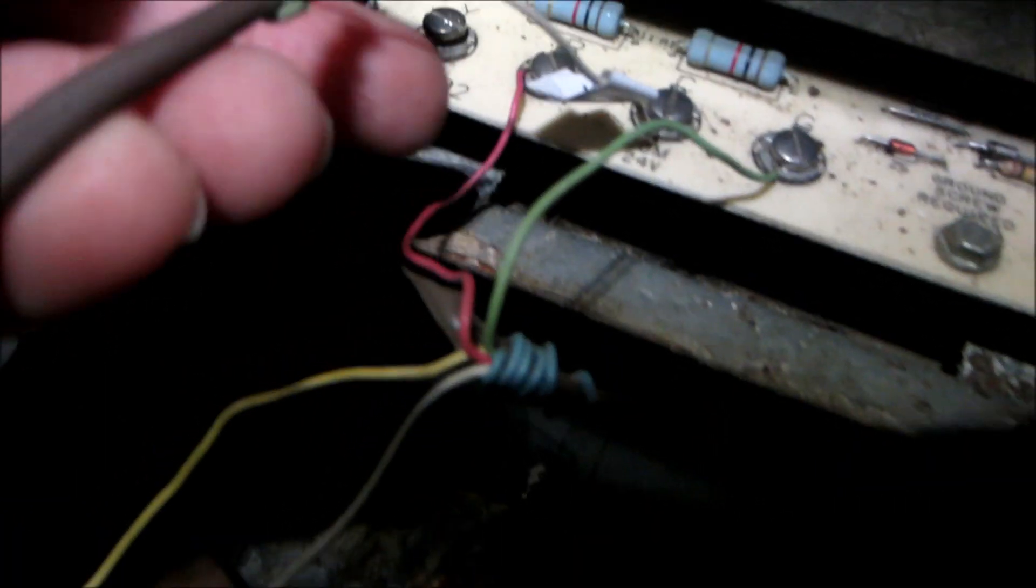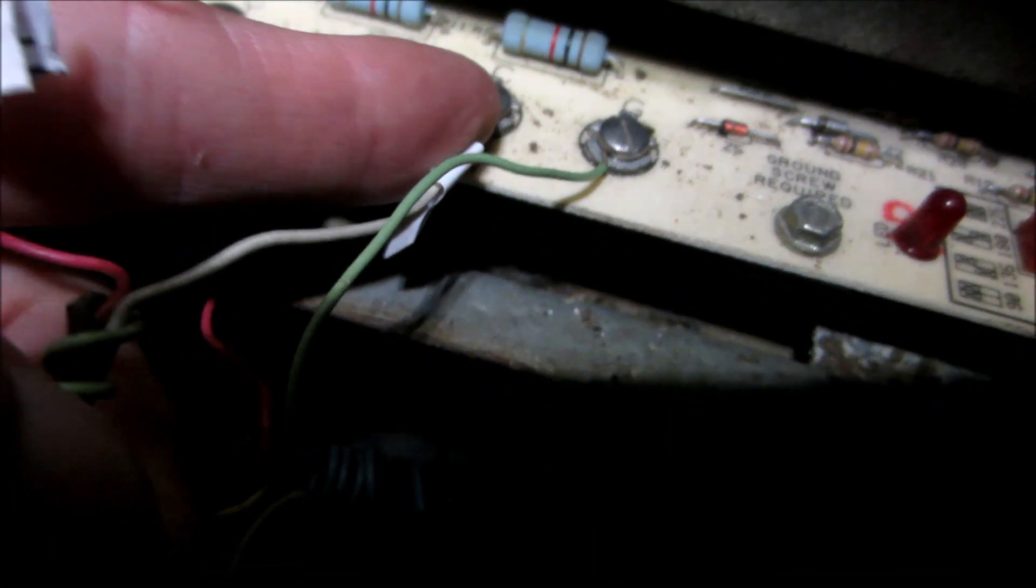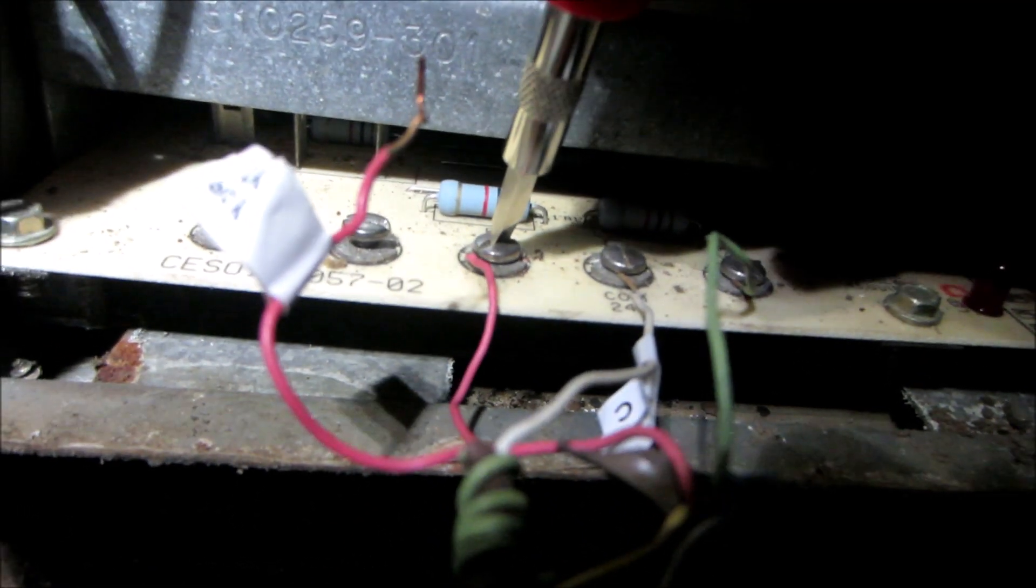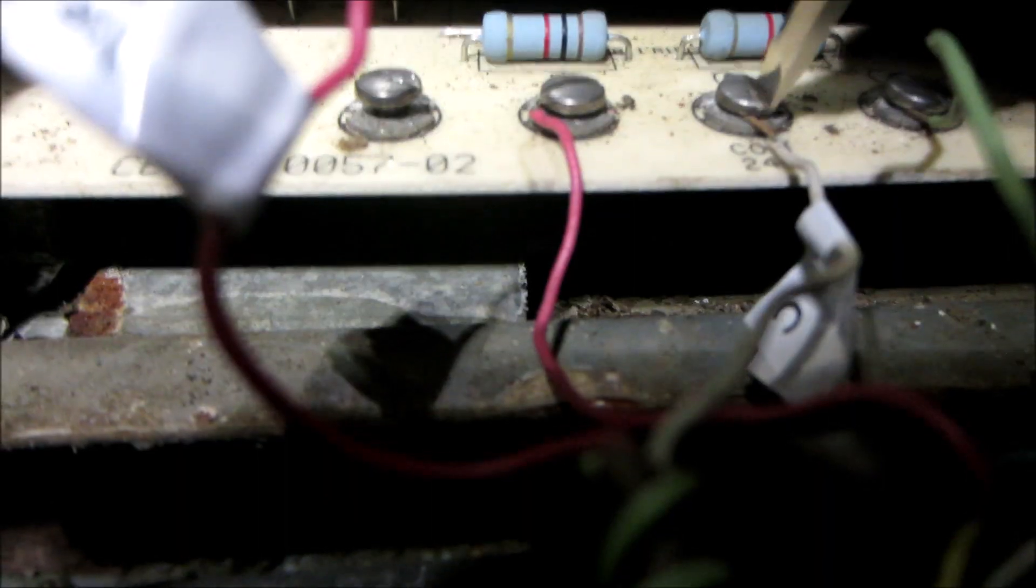You see the Y right here. This wire is from the outdoor thermostat, which I'm going to keep to the Y, but this yellow one is from the indoor thermostat. I'm going to go ahead and pull this off. Here's the yellow. These are coming out of this one right here. So now I've got only two coming from the outdoor. This one labeled in the C which will stay there, and this red one that was in the Y. This is why you label these. I loosened that one.